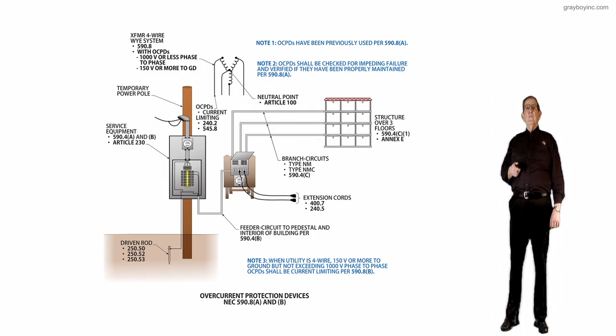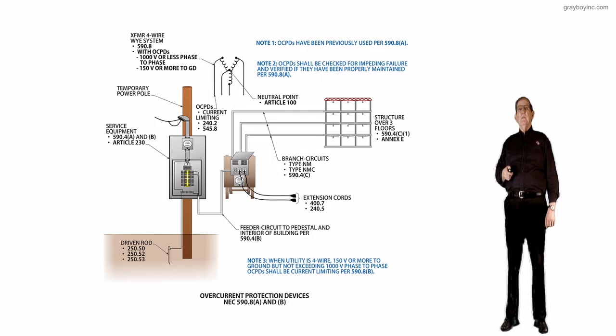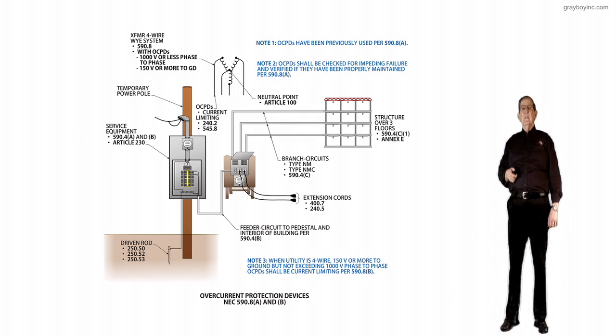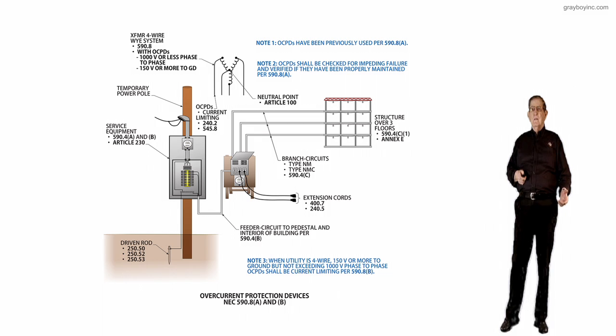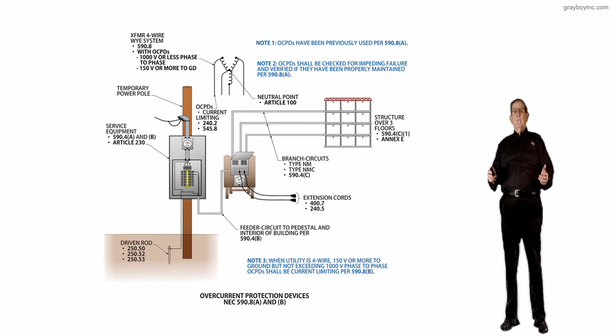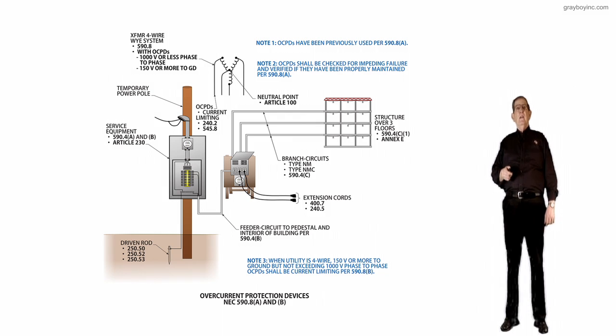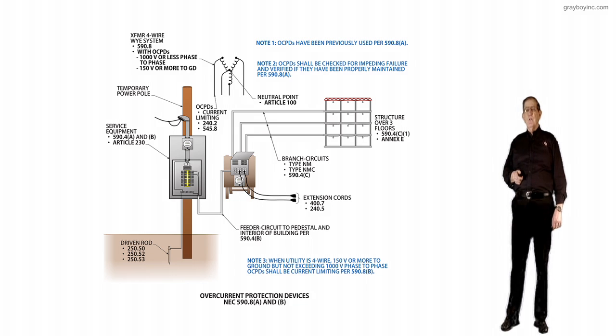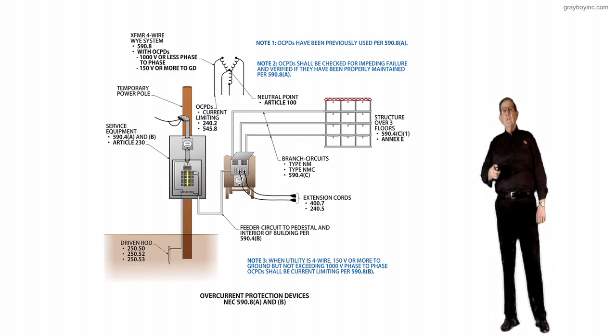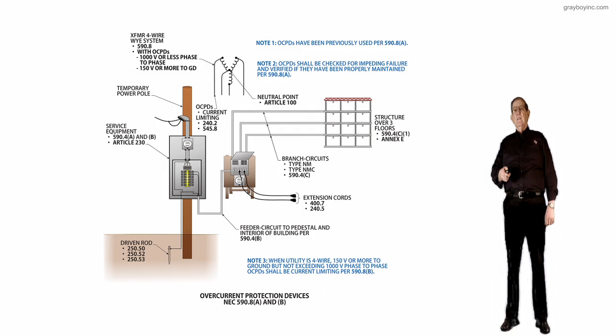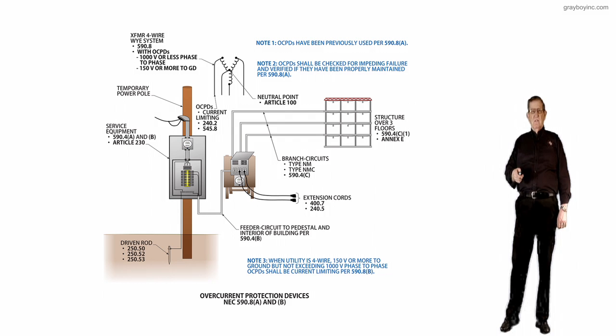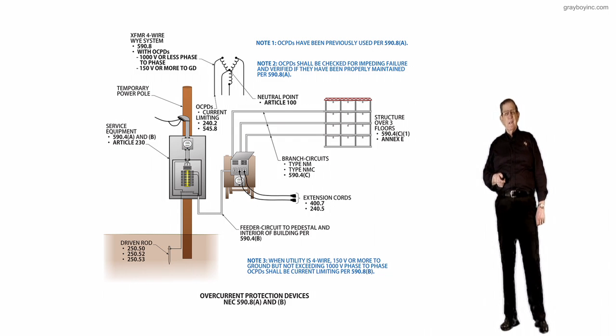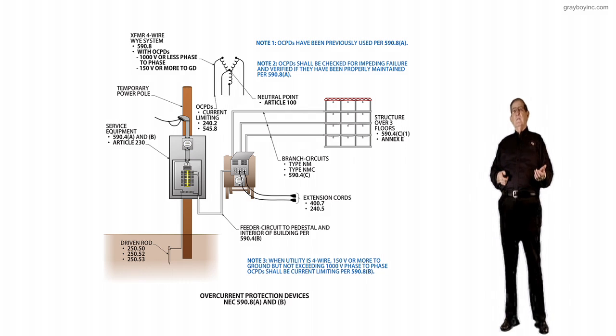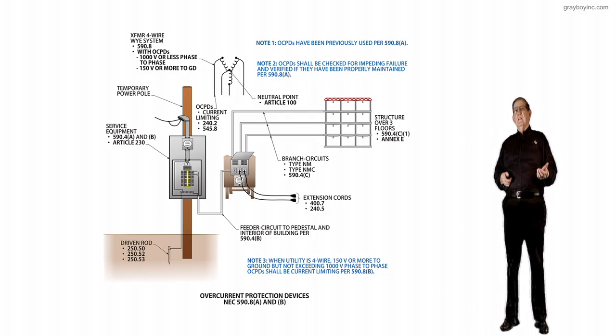And if you review the temporary pole there with the service equipment, meter, etc. on it, then notice that has to comply with Article 230. No wiring method less than, no installation less than. And we know 590.4(A) and (B), Article 230, stresses this. But now once we have an overcurrent device, then we run this feeder over to the pedestal. Then we know that could be just flexible cord, hard usage or extra hard usage, depending on where we route it and use it.